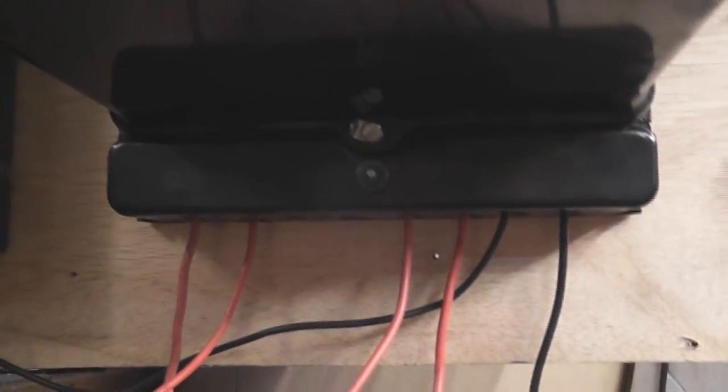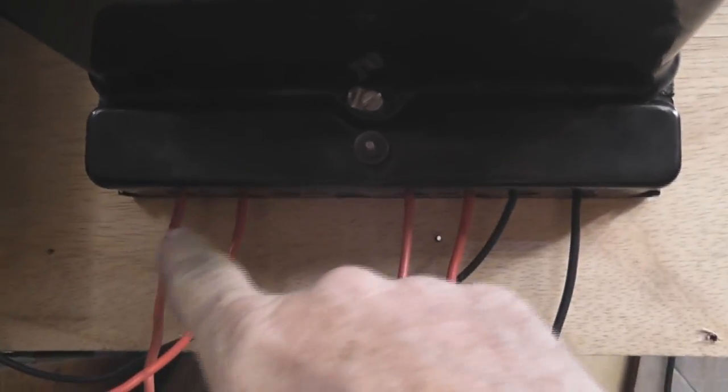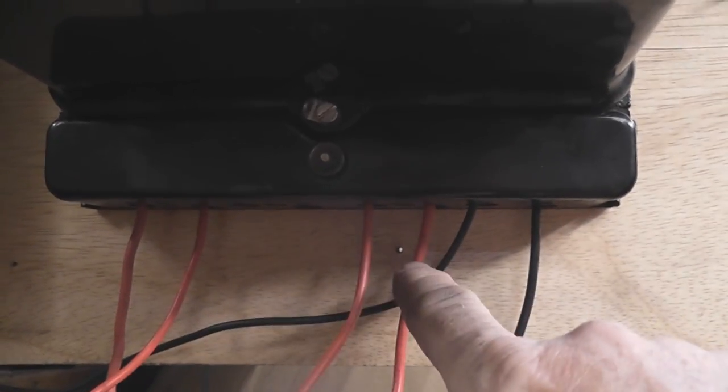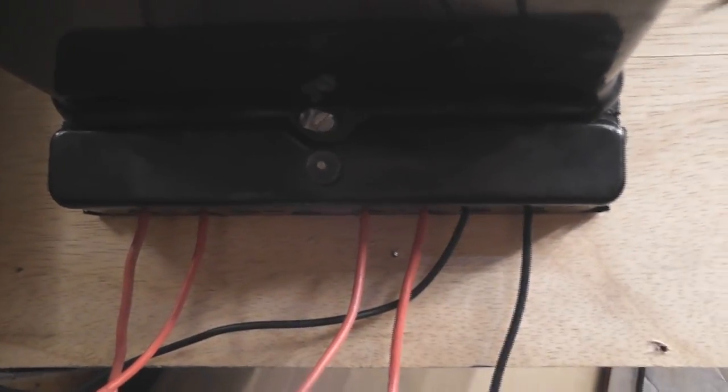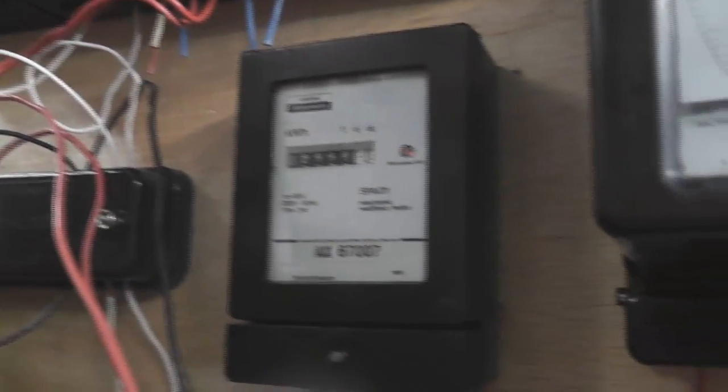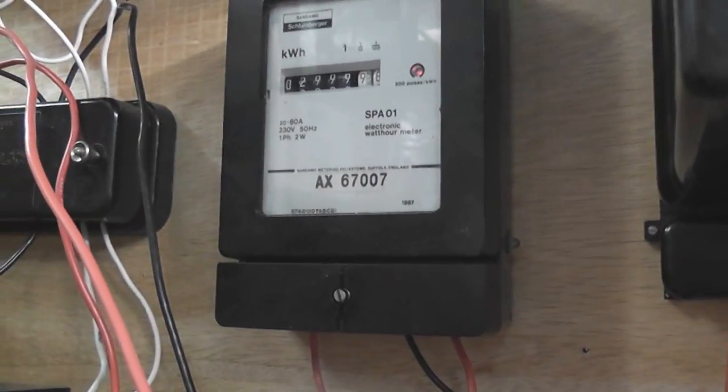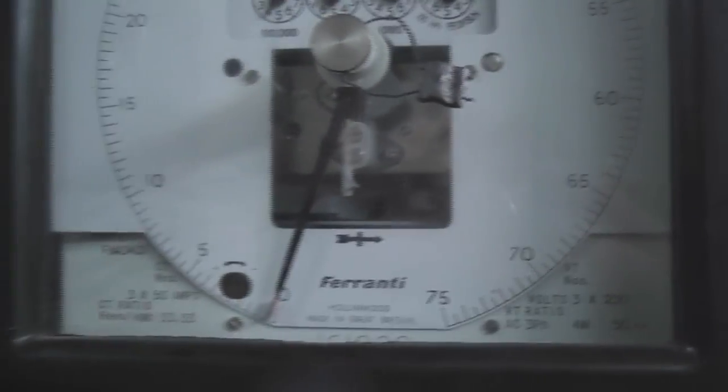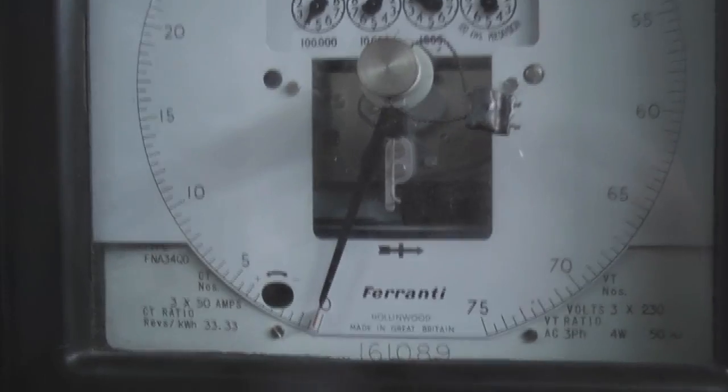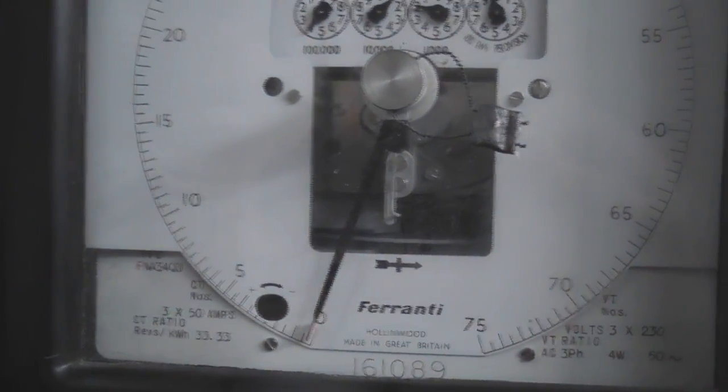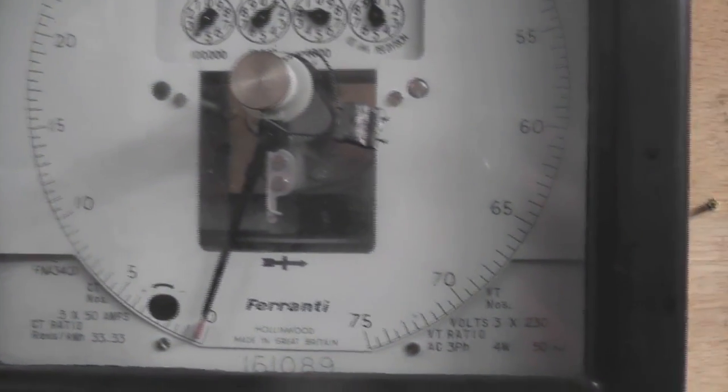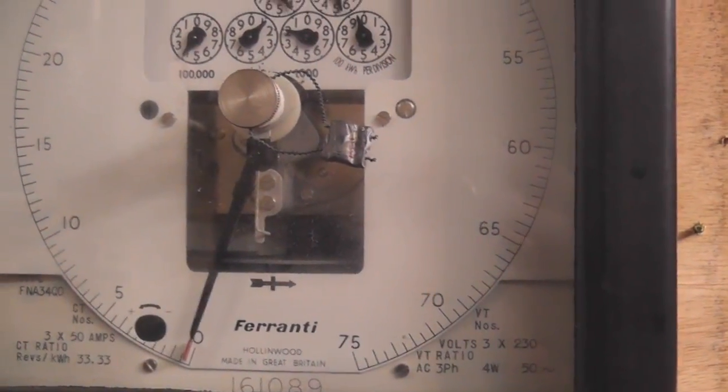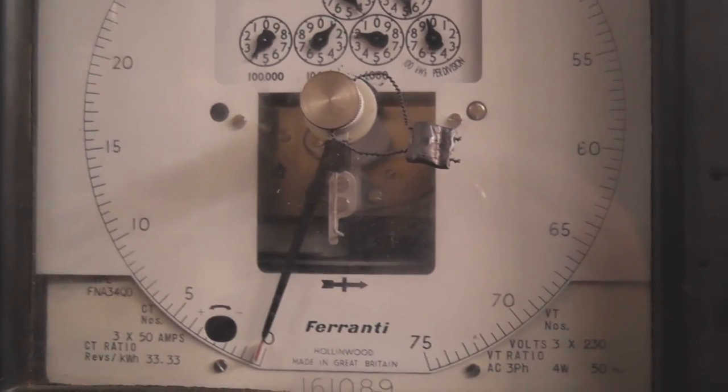So the way I've wired this up is one element and the other element more or less in series so the source comes out of the test block goes into the red elements, from there it goes to the Schlumberger test meter, back out of the Schlumberger back into the Ferranti and I'm just going to do a dial test and see how the maximum demand indicator is performing. See if it actually works.